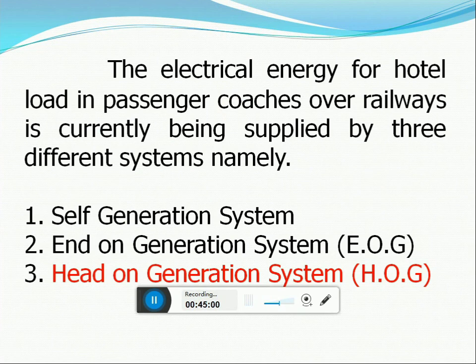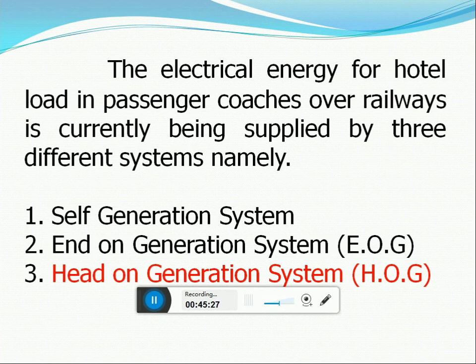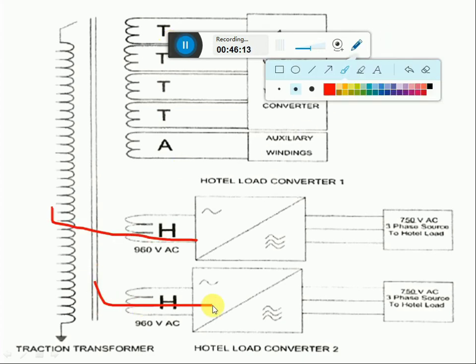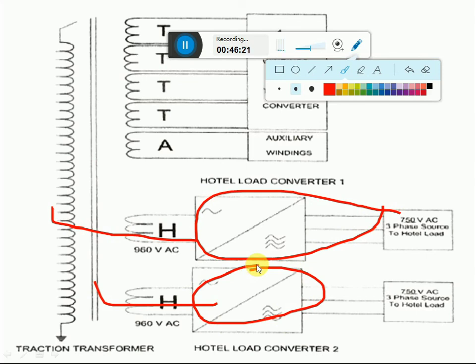This supply can be given by 3 ways: one is the self-generation system, the end-on generation system (EOG) using two generators at the ends, and the Head-on Generation (HOG) system where supply is given from the loco by keeping one extra hotel load winding. From the hotel load winding it is stepped down. In the HOG system, two hotel load converters are provided with two additional windings. The supply taken from the main winding is converted from single-phase to three-phase, and that three-phase supply is given to the coaches.